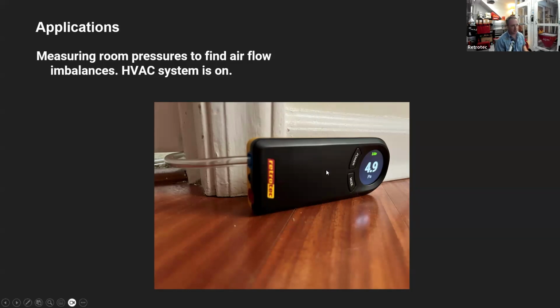So here, all we're doing is we have this bedroom door shut. We have a tube tossed under the door, shut the door, and we see with the HVAC system running that this house is about 5 pascals positive. With pressure getting that high, there's definitely some chance of discomfort in that bedroom, especially if the occupants sleep with the door closed.